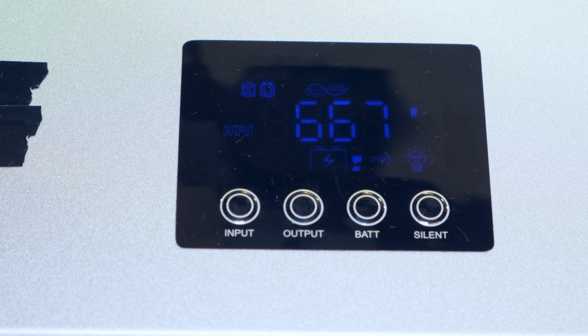You can see that it is well above the 600 watts maximum rated for this unit. And that's why I said that the protection should not come in if there's just a bit of an overload. There you can see the inverter is actually functioning fine. It's got its own protection and it will cut off if there's a problem. But the circuit breaker is there for a fault or a heavy overload. So there we can see that 620, 630 watts, it didn't trip the circuit breaker. And there it's basically full load and the circuit breaker is still in the on position.